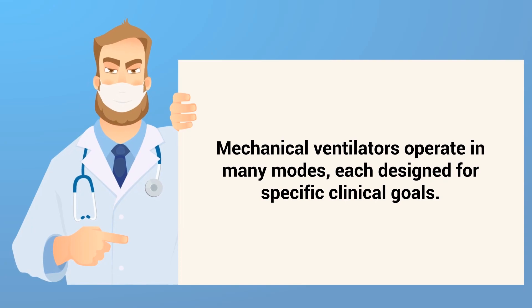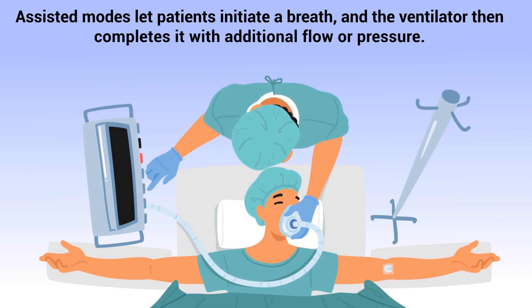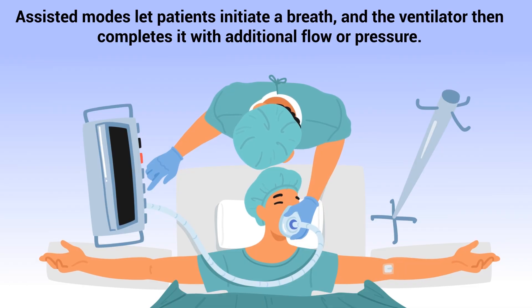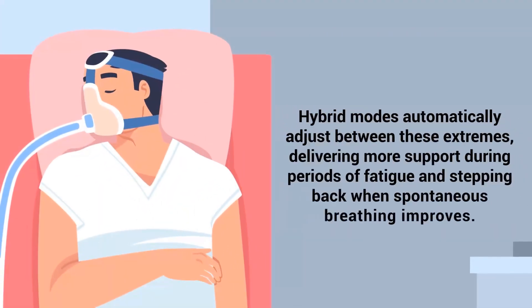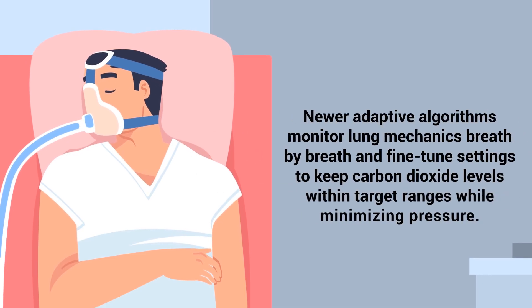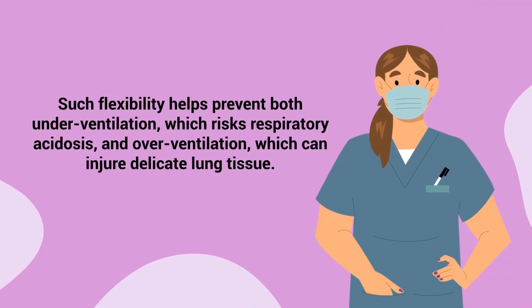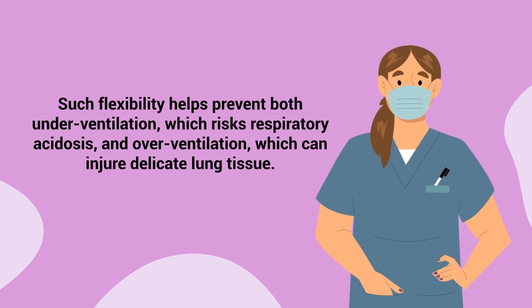Mechanical ventilators operate in many modes, each designed for specific clinical goals. Controlled modes give the machine full authority over the timing and size of breaths, suitable for patients who are deeply sedated or paralyzed. Assisted modes let patients initiate a breath, and the ventilator then completes it with additional flow or pressure. Hybrid modes automatically adjust between these extremes, delivering more support during periods of fatigue and stepping back when spontaneous breathing improves. Newer adaptive algorithms monitor lung mechanics breath-by-breath, fine-tuning settings to keep carbon dioxide levels within target ranges while minimizing pressure, helping prevent both underventilation and overventilation.